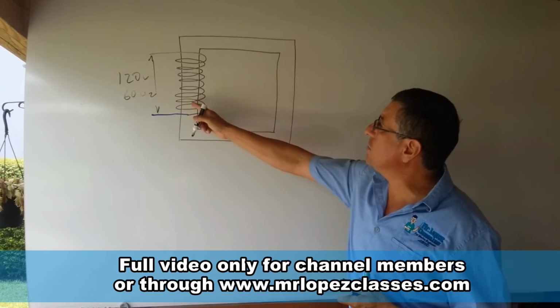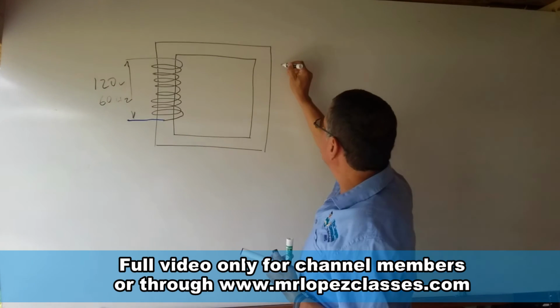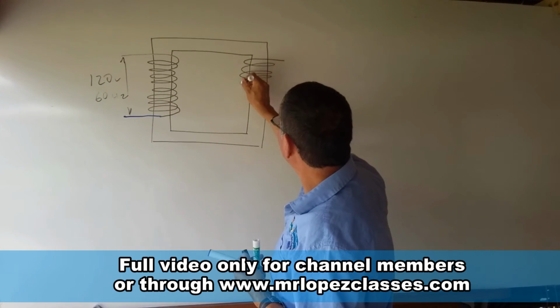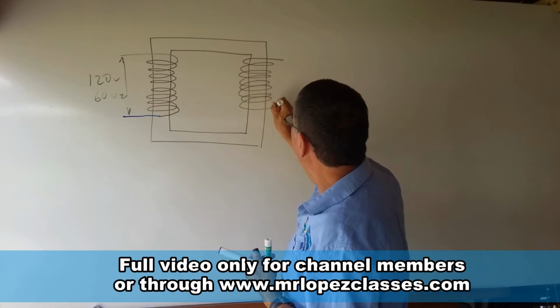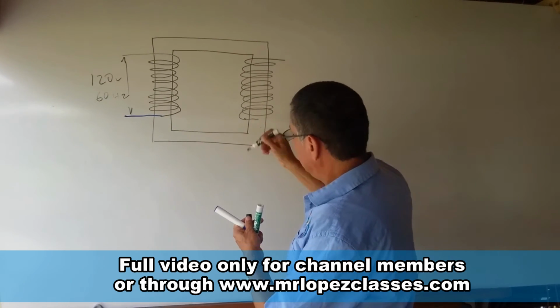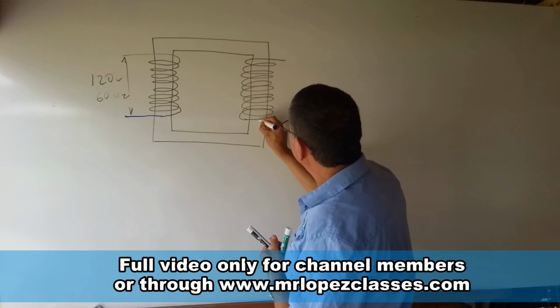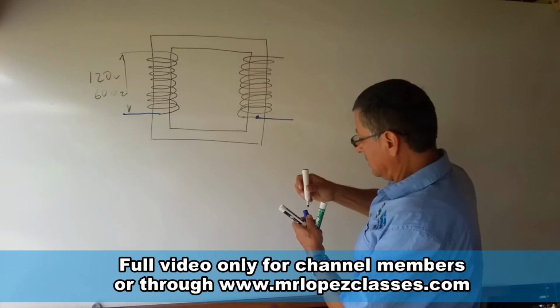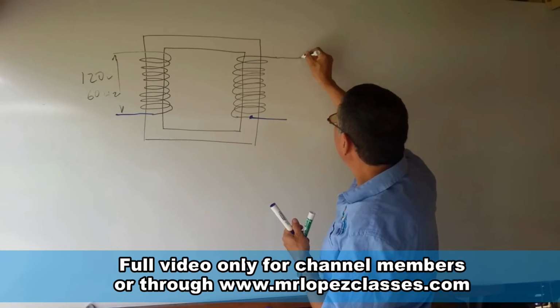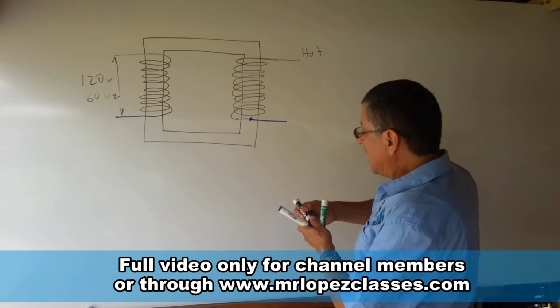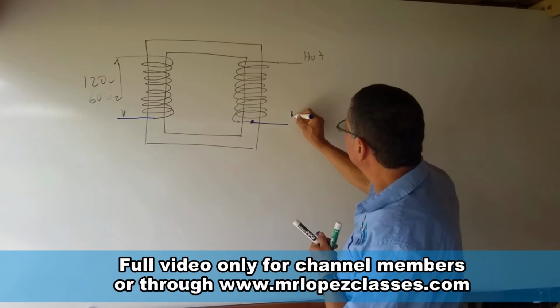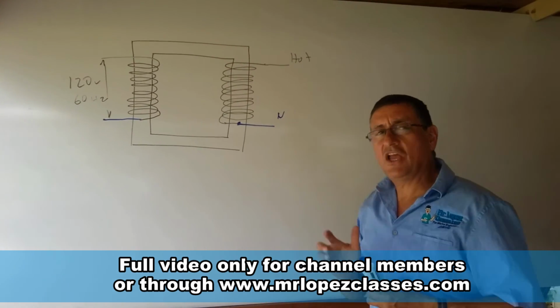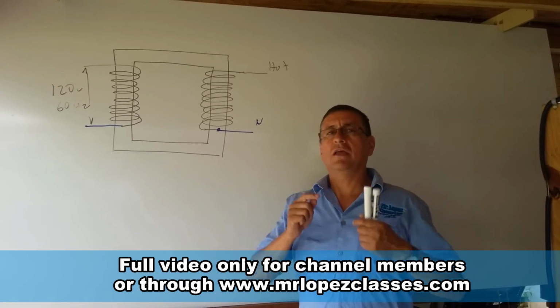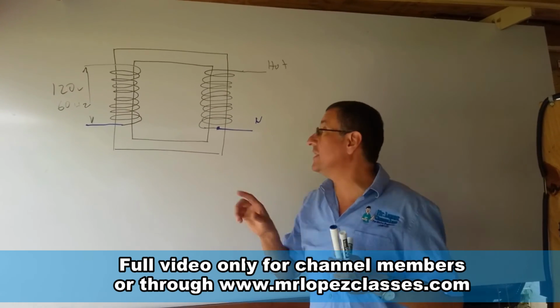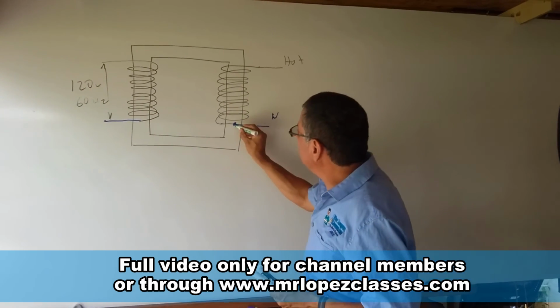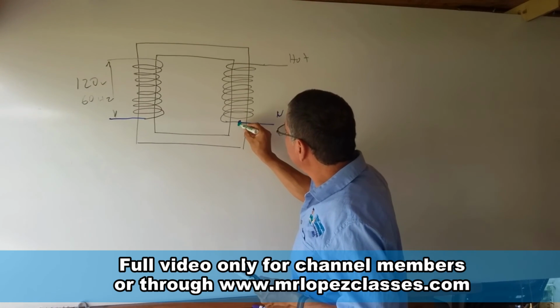If I have the same amount of coils in the secondary, of course I have 120 volts. And this is the neutral, and after this point, this end will be the hot line, and this end will be the neutral. Remember, only at the source of the power are neutral and ground together. This is the source of the power. At this point, the ground is together with the neutral.